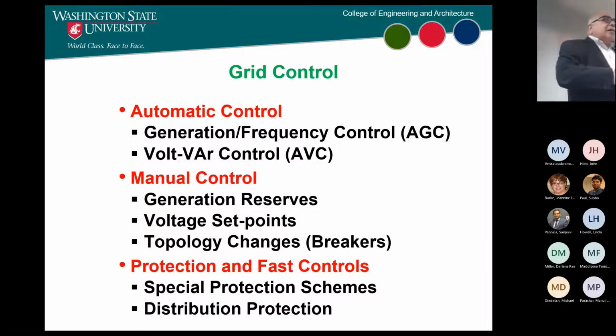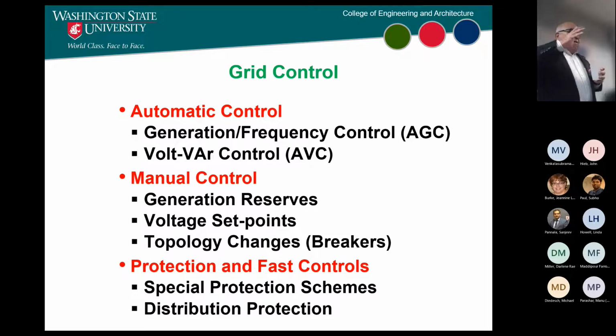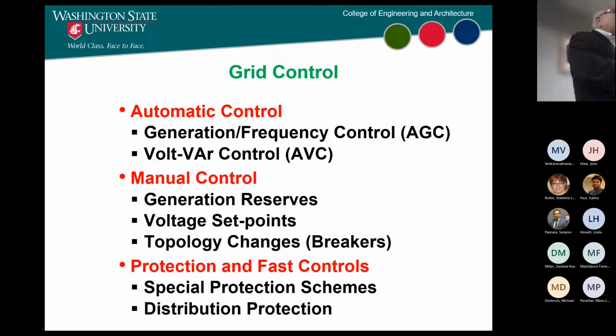In many other countries they do regional voltage control, similar to AGC, and that may come into play here too. In fact it'll probably become more common because you've got so many generators that you can't expect a substation-level generator to be held up by only one generating source when you have so many small generators.